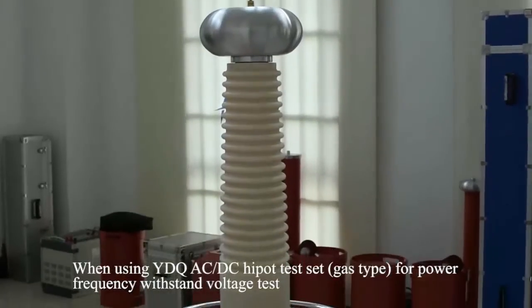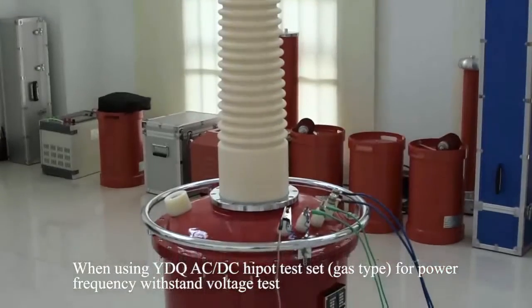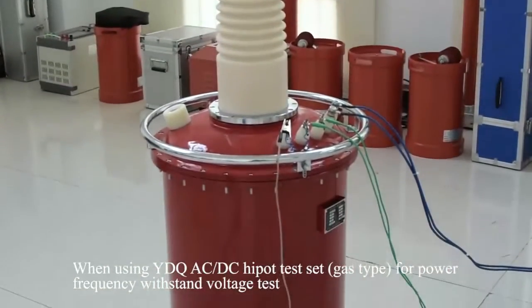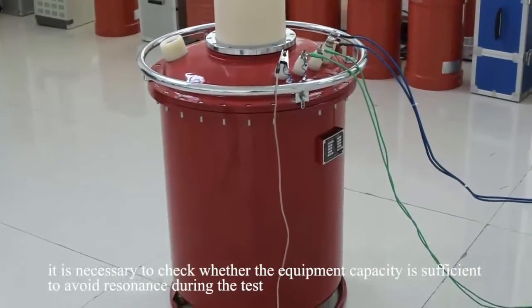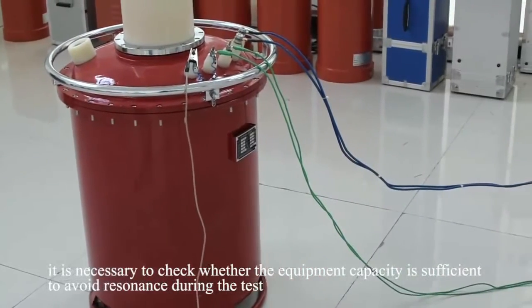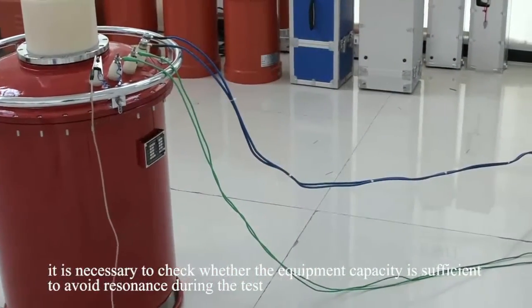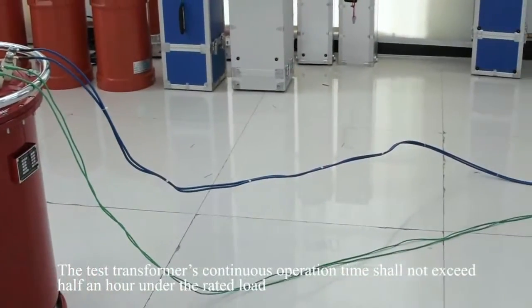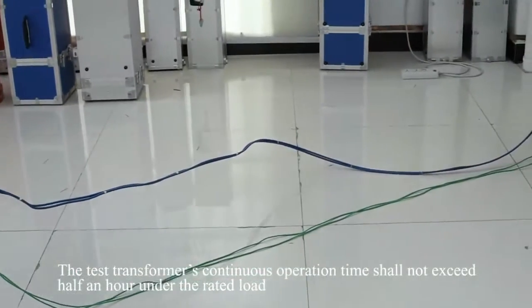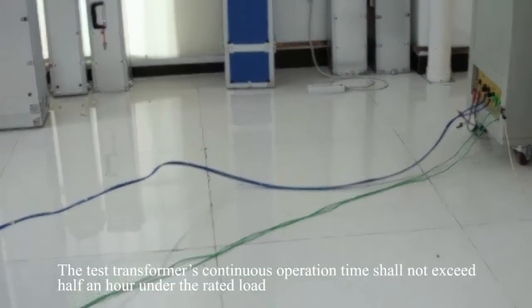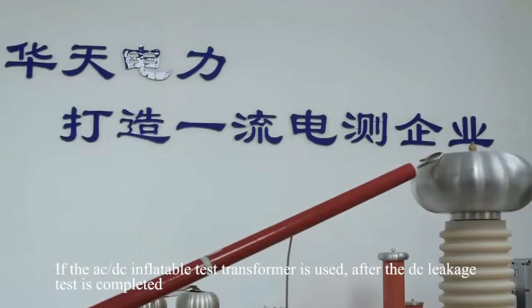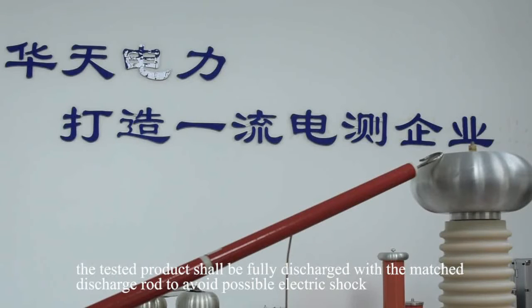When using the YDQ AC/DC Hipot test set gas type for power frequency withstand voltage test, it is necessary to check whether the equipment capacity is sufficient to avoid resonance during the test. The test transformer's continuous operation time shall not exceed half an hour under the rated load. If the AC/DC inflatable test transformer is used after the DC leakage test is completed, the tested product should be fully discharged with the matched discharge rod to avoid possible electric shock.